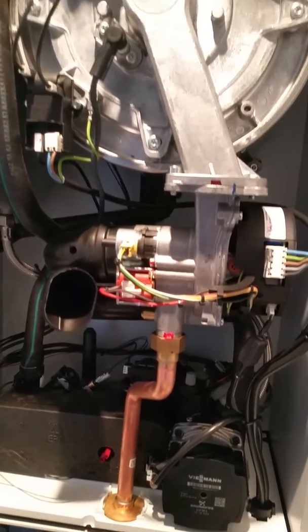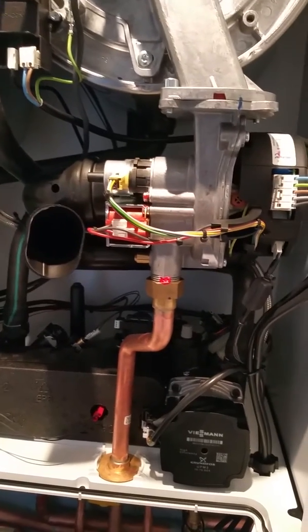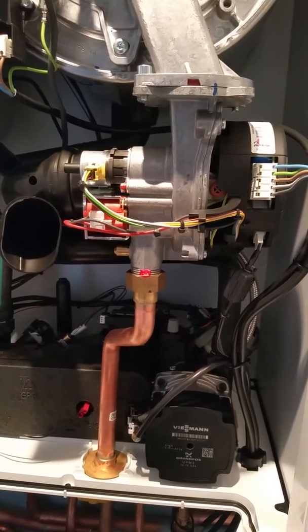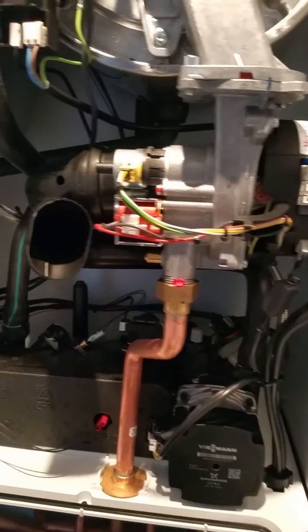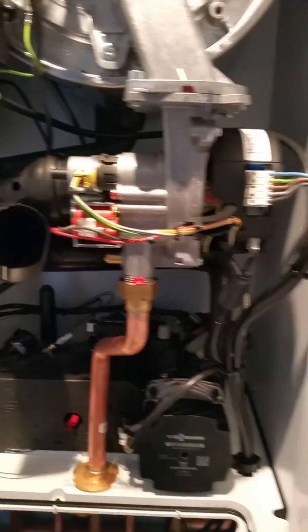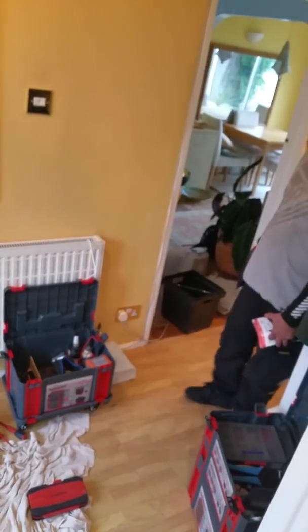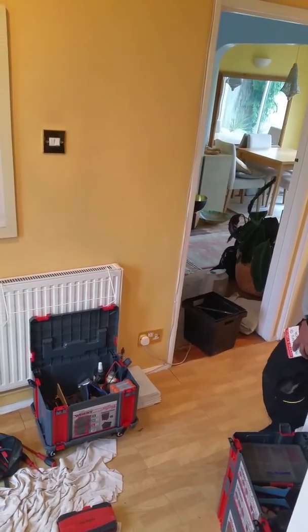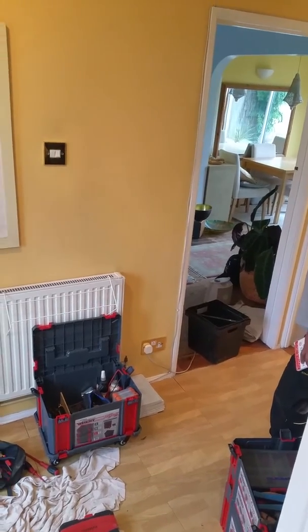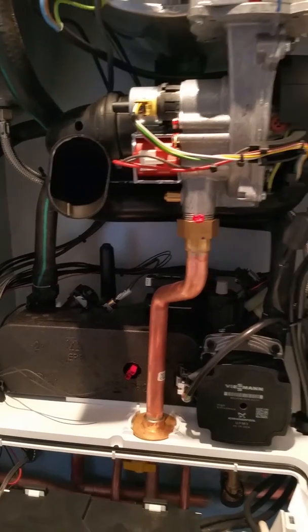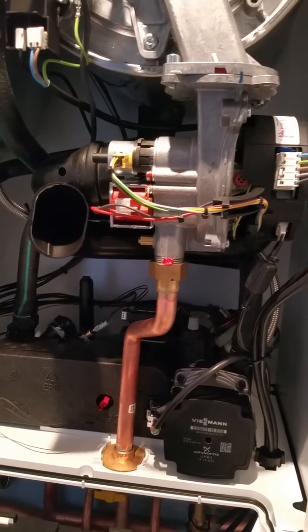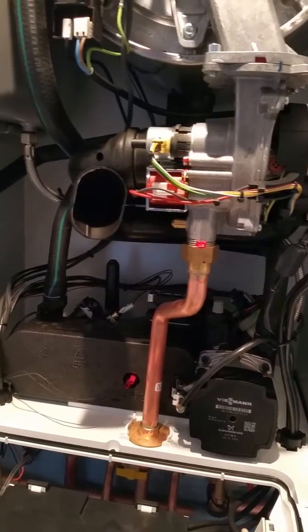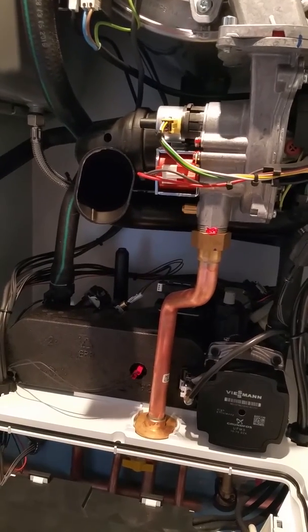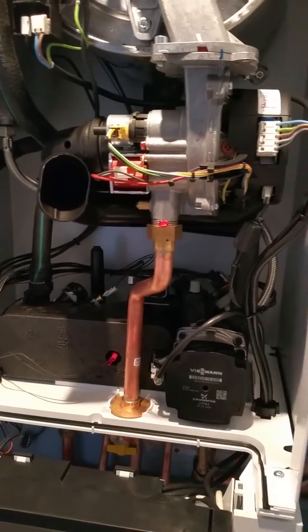35 kilowatt combi, so that's a 20:1 modulation ratio, and this is a small house, 2 or 3 bedrooms I think. As a matter of interest, I've had a little 2 kilowatt heater running over there while I've been working here, and the house has been warm and comfortable with just 2 kilowatts, and it's probably about 5 or 6 degrees outside, maybe a bit cooler. So I'd imagine we're not going to need more than about 8 kilowatts to heat the whole house.